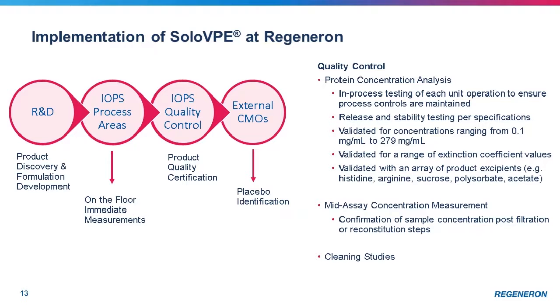Various analytical techniques require confirmation of sample concentration during the assay, such as after a filtration step or after a reconstitution step. SoloVPE makes these steps more efficient as operators do not have to stop mid-assay to dilute samples and manually perform calculations.